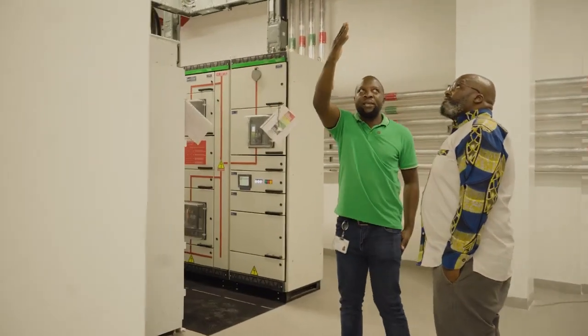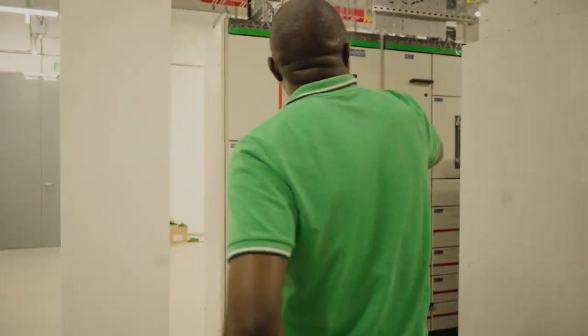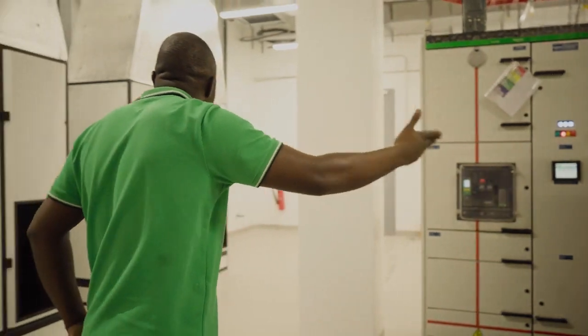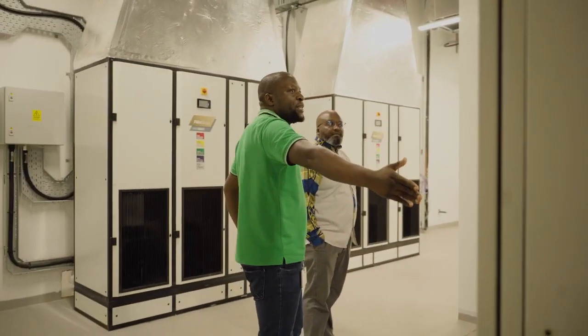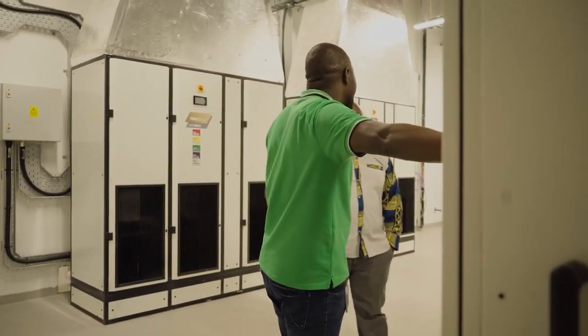When power comes in, it's evacuated from the TX, the transformer, to the input board of the UPS. From here it's taken to the UPS, conditioned, then up to the output board. This is where we now distribute our power to our critical loads.